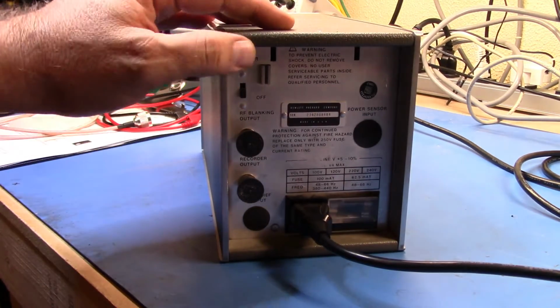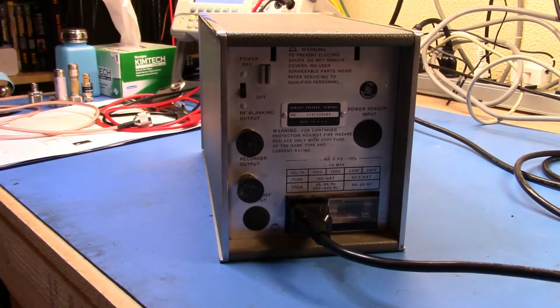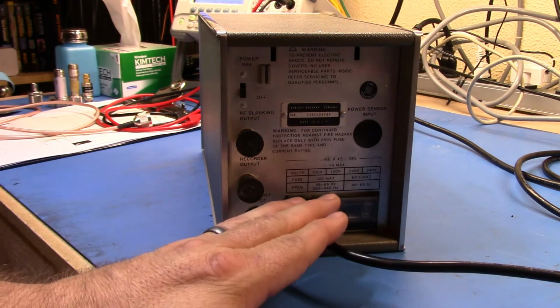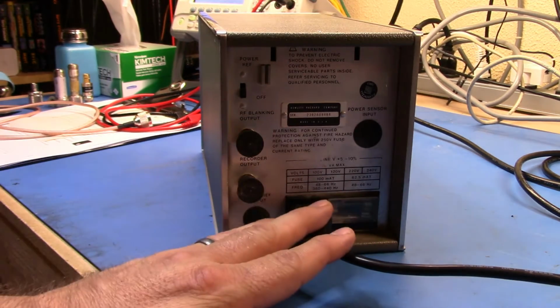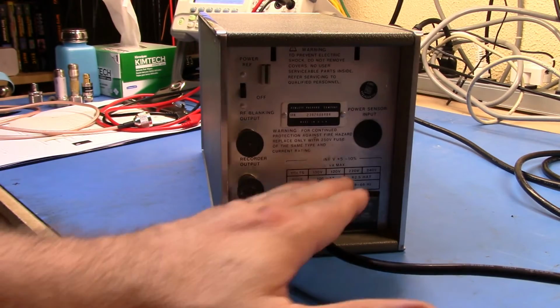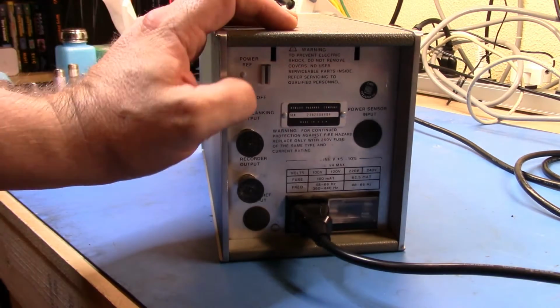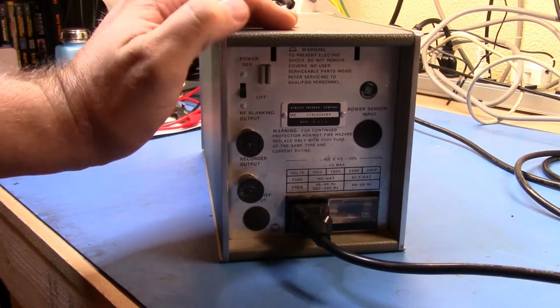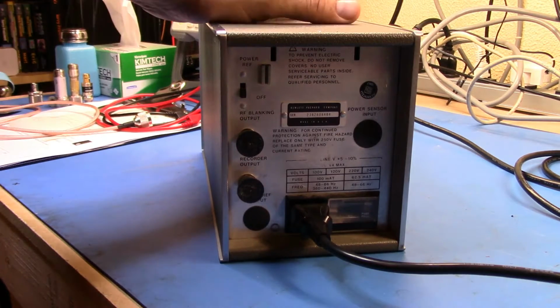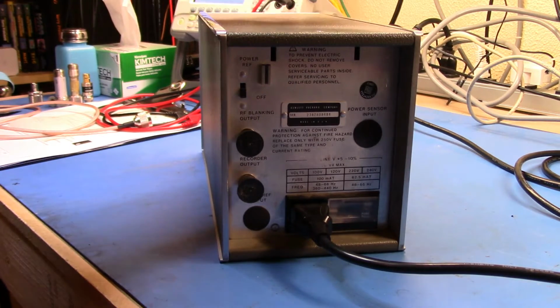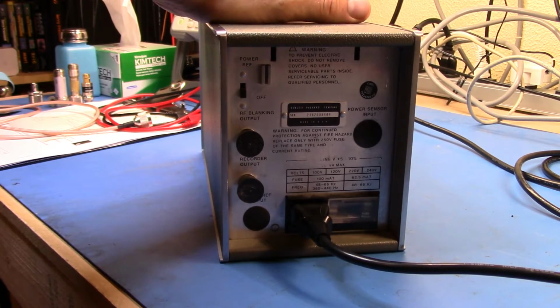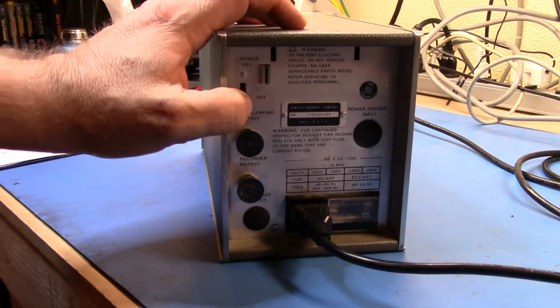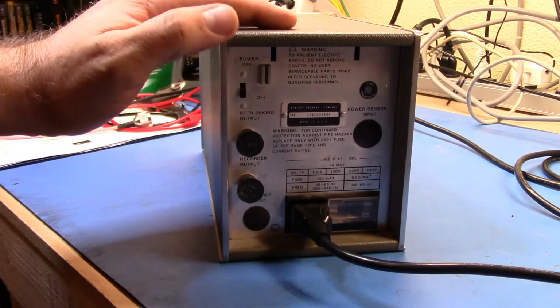It just occurred to me that I didn't show you the back of the instrument. Here's the back. Obviously the power cord goes in, multi-voltage. It has a very simple switch to turn the power reference on and off. Typically, you don't want to be running those power references 24/7, so you want to give it a chance to warm up and then do your reference check, and then switch it off.